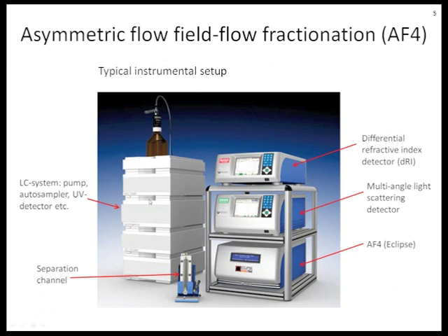Due to the low shear forces and gentle separation mechanism, we can also fractionate very fragile samples such as aggregated polymer structures. This is what a typical instrumental setup looks like: we have an LC system that generates the flows and handles sample injection, the separation channel where the actual separation takes place, the AF4 box called the Eclipse which contains valves controlling different flows, a multi-angle light scattering detector, and a refractive index detector for concentration determination.